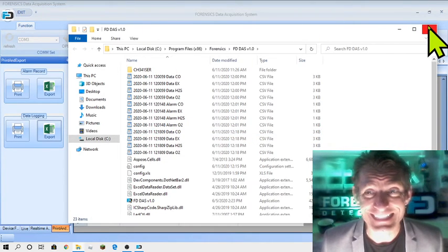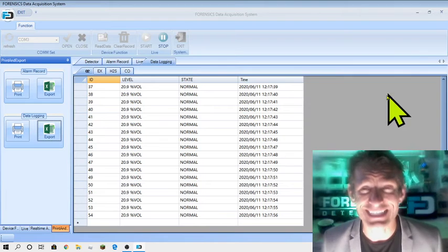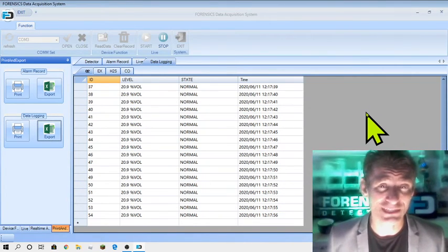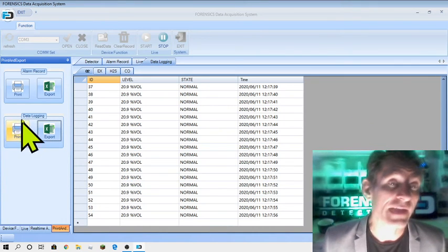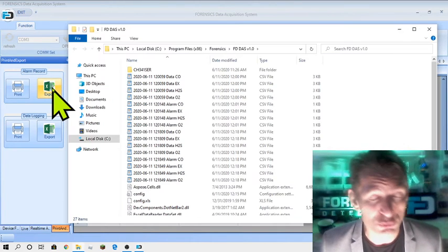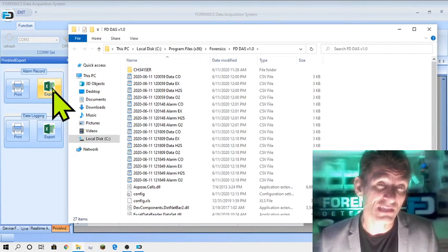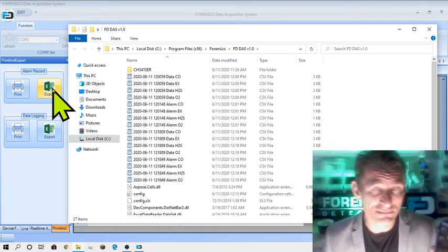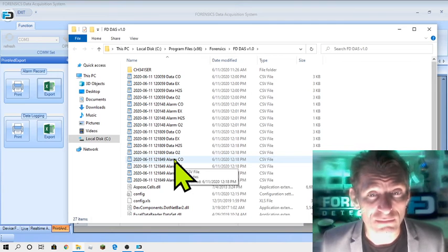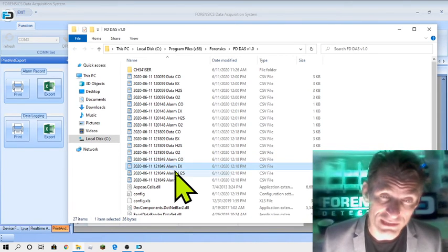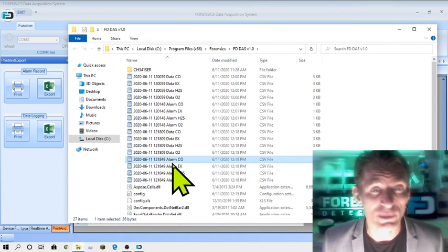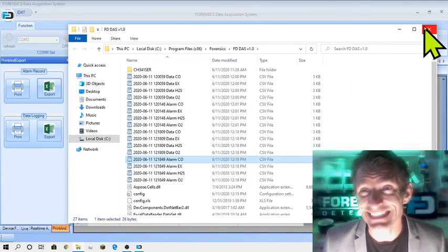And that's basically it. It's in a CSV file format. It's the most flexible file format for data acquisition, manipulation in Excel or any other spreadsheet. Now, we have another functionality here. It's called the alarm record export. If alarm was triggered or the detector itself has a history of triggering the alarms, it will extract that information and it will dump it into these alarm files so you can report these or have them as a reference. Okay, so this is where they are kept, and again, that is also in CSV file format.